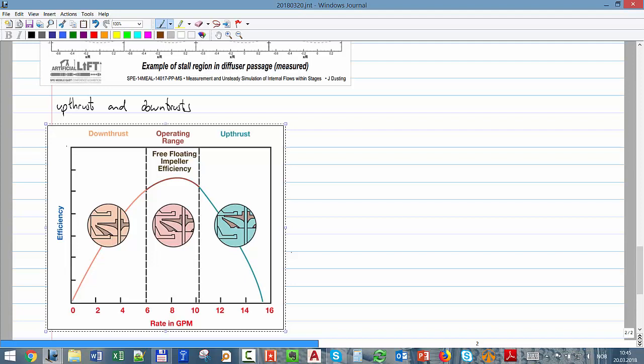You can also include some holes at the top of the impeller to reduce that effect. Like tiny holes on top of the impeller in order to reduce that pressure differential, therefore this effect. Yeah, you have other sort of tricks, but what Juan Manuel is saying is that sometimes you connect.